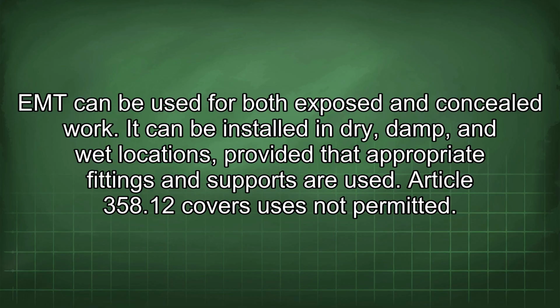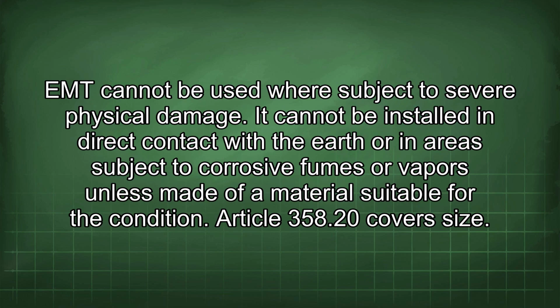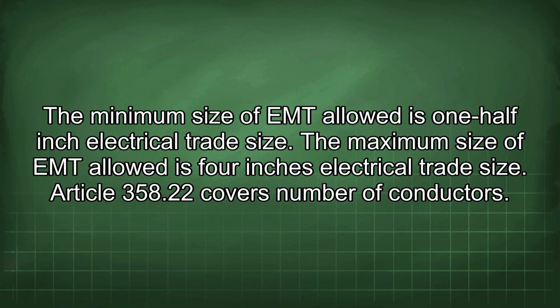Article 358.12 covers uses not permitted. EMT cannot be used where subject to severe physical damage. It cannot be installed in direct contact with the earth or in areas subject to corrosive fumes or vapors unless made of a material suitable for the condition. Article 358.20 covers size. The minimum size of EMT allowed is 1/2 inch electrical trade size. The maximum size of EMT allowed is 4 inches electrical trade size.